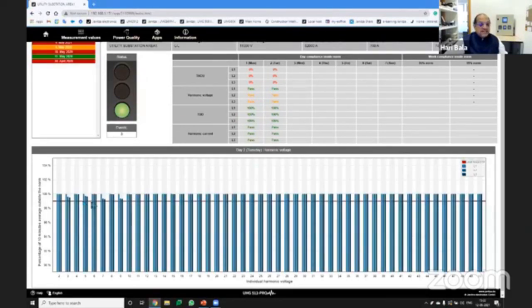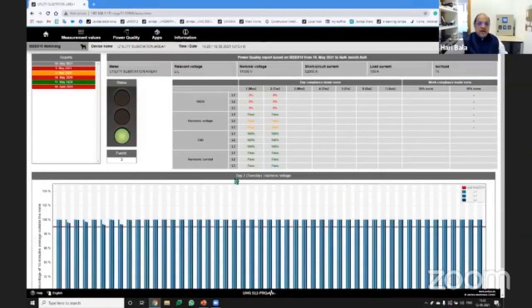And then we have the information of individual harmonics. This is how the IEEE works, where you write your nominal voltage, insert your short circuit current and your load current, and then the ISC by IL value is calculated. Accordingly, your compliance is tested in the meter and then given as a web page for you. That's another feature of this one.